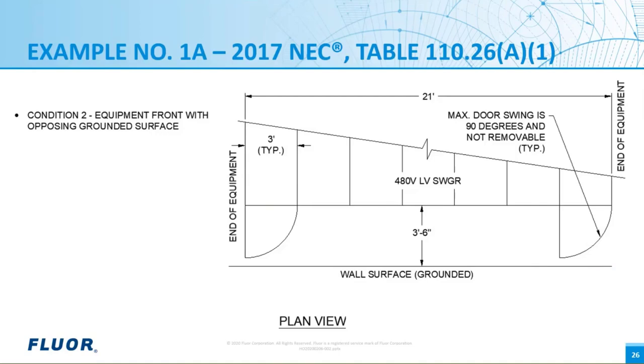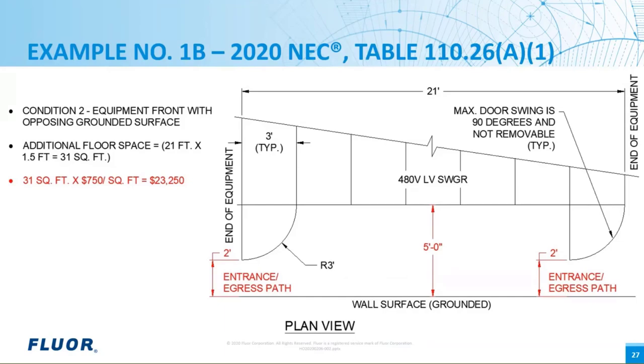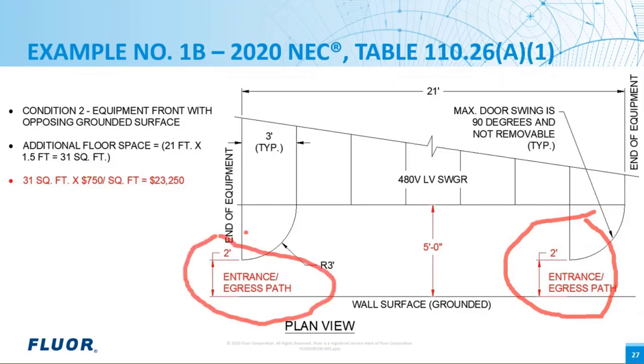What we're trying to do is simplify the diagrams because there's an infinite number of pieces of equipment and installations that are available. This is the exact same equipment as the previous slide, but now we have increased spacing. Take a look at the red text at the end of the equipment. According to the 2020 NEC, we must have a 24-inch minimum entrance and egress path included when the doors to the equipment are open. This makes the substations bigger and it increases the cost of the buildings. For example, in this installation, the cost increased by $23,000 based on $750 per square foot for the building, just for the extra space in front of the equipment.